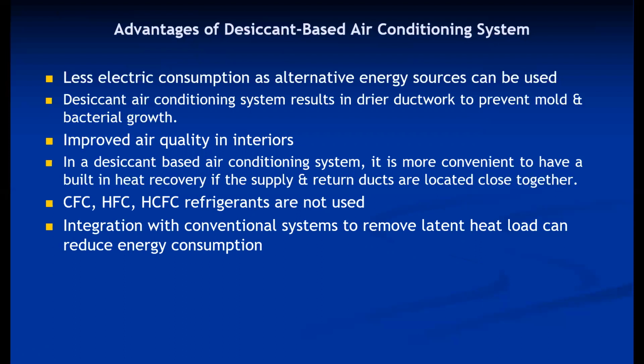Integration with conventional system to remove latent heat load can reduce energy consumption substantially. That we have already seen in two practical desiccant systems, that is liquid desiccant air conditioning system and hybrid solid desiccant air conditioning system. In both cases, the load on air conditioning coil is substantially reduced. Its operational cost is obviously low because as the load reduces, operational cost is also low.